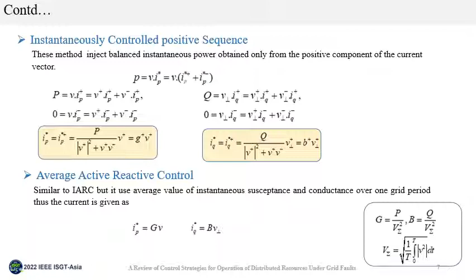The third strategy was the average active reactive power control. This strategy is similar to IARC, but instead of the instantaneous value, it focused on the average value of the instantaneous susceptance and conductance, and this average value can be derived in one grid cycle by using this. After putting in the values, these are the current reference equations for the active and reactive components.